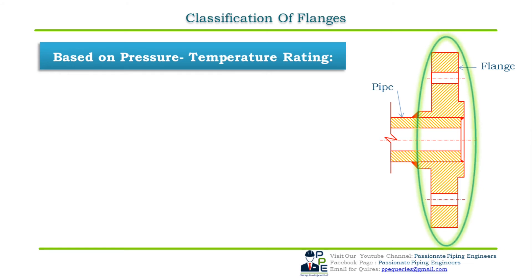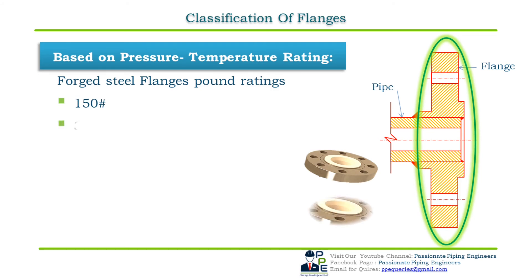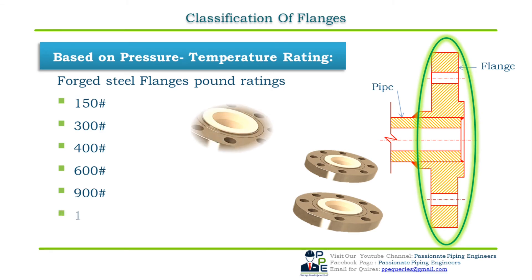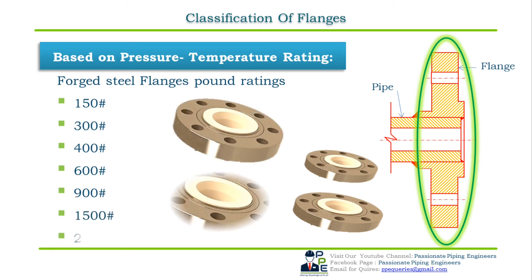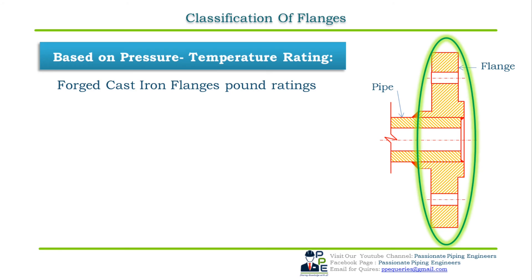Based on pressure-temperature rating: the pressure-temperature rating chart in ASME B16.5 specifies the non-shock working gauge pressure to which the flange can be subjected at a particular temperature. Pressure class or rating for flanges is given in pounds. Forged steel flange pound ratings are: 150, 300, 400, 600, 900, 1500, and 2500. Forged cast iron flange pound ratings are: 25, 125, 250, and 800.